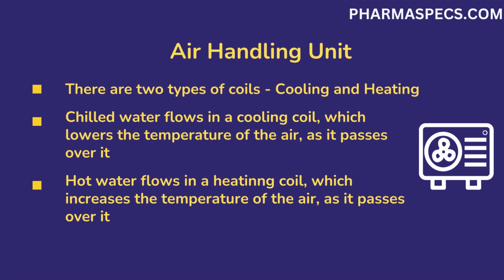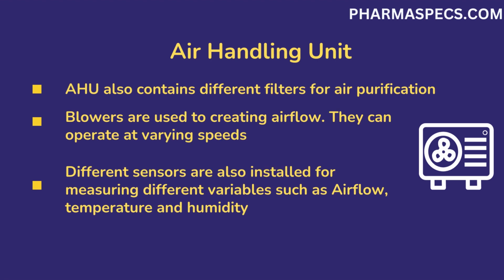In the coil section, there are two types of coil, cooling and heating. In the cooling coil, chilled water circulates to cool it. When air passes through it, it lowers the air temperature. Air also becomes dehumidified in this section. In the heating coil, hot water is circulated. When air passes through it, it increases the air temperature. The cool air resulting from the cooling coil and the hot air resulting from the heating coil decrease and increase the temperature of an area simultaneously.